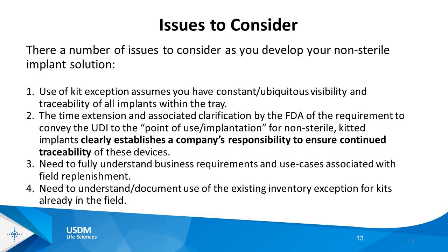The issue became moot, if you will, because in the process of moving from the proposed to final rule, the direct marking requirement was removed. So not being able to direct mark an implant doesn't solve what I consider to be the new threshold that has been created, which is UDI of an implant needs to be available at the point of implantation, full stop.